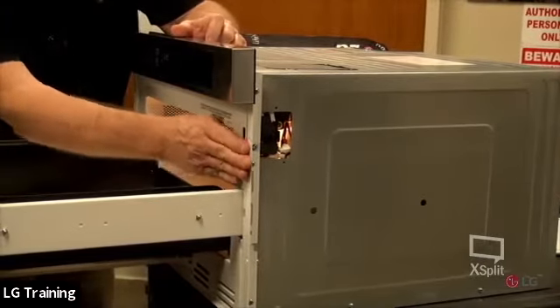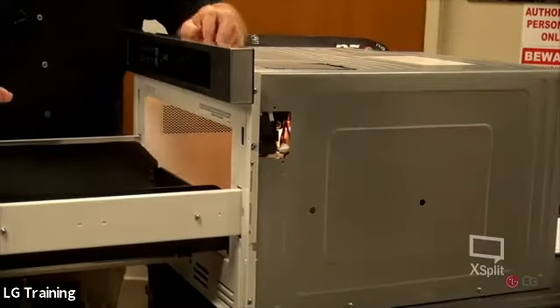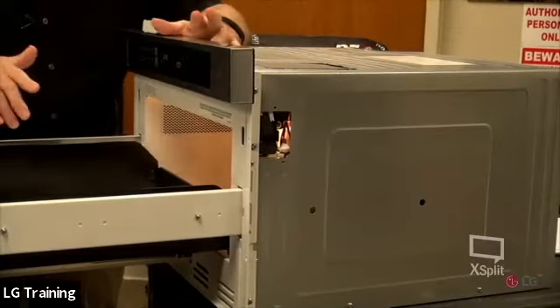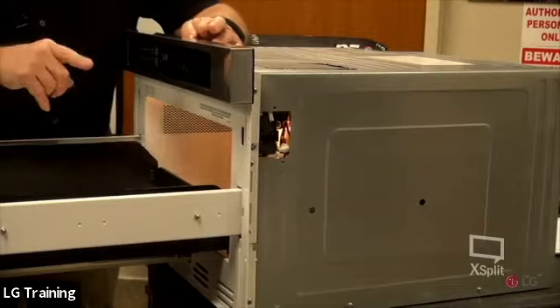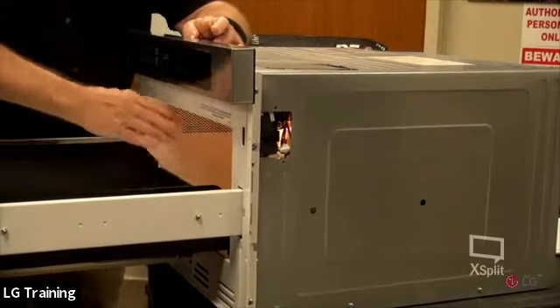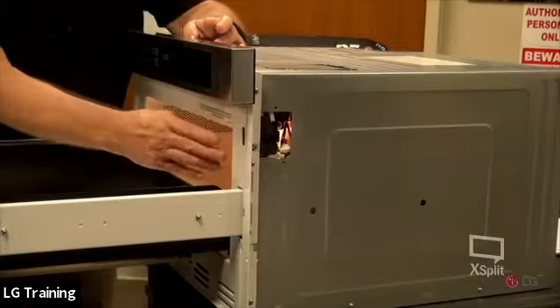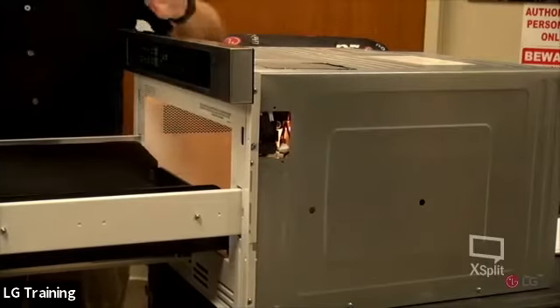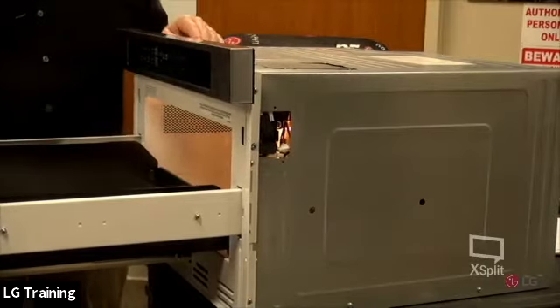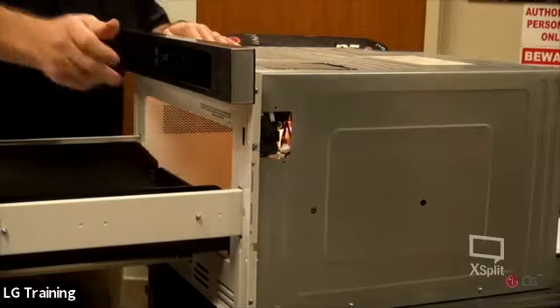Where when these close, this switch closes, but maybe something is keeping this from going all the way back in. Now I have a spot here where I can get excessive radiation leakage, so two switches monitor that to make sure we're running under a safe condition. Both of those switches have to be closed when the door is closed. Of course, your monitor switch is going to be open.